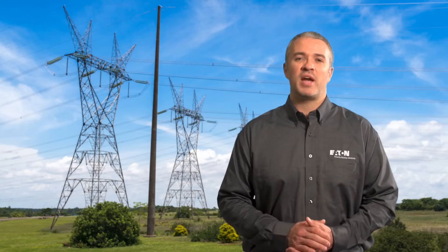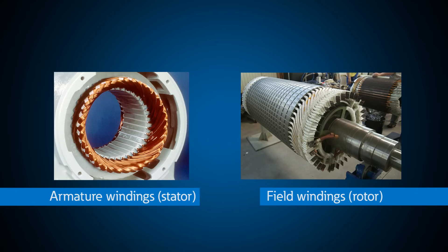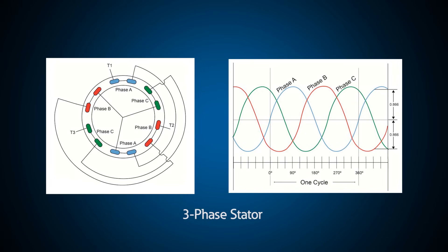The core is generally made of a low-loss magnetic material, used to support the coils of the armature windings and as a return path for the lines of magnetic field. The magnetic field created on the rotor induces a current onto the armature windings. The stator windings tend to be larger, highly insulated, and more complex than the field windings because they must carry the generated power at a much higher voltage. A three-phase stator consists of three windings where, for each phase, there is one group for each rotor pole. Each group has an output lead 120 degrees from one another, and the leads are typically Y or star connected.